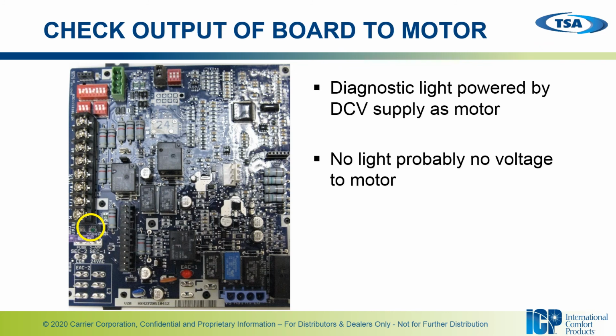Okay, one quick giveaway on the variable constant torque motors. On that specific furnace, the LED light on the control board is powered from the same DC volt signal supply as the motor. So if you have no light on the communication LED on that control board, chances are you do not have the DC volt power supply going to the motor as well, in which case you have a defective control board, and I would suggest you replace the control board at that point. However, if the light is present, further diagnostics is required.